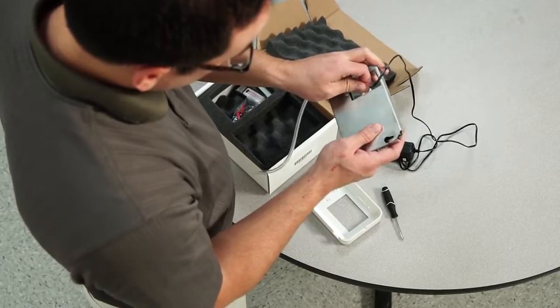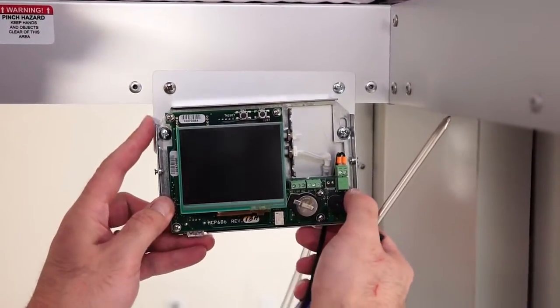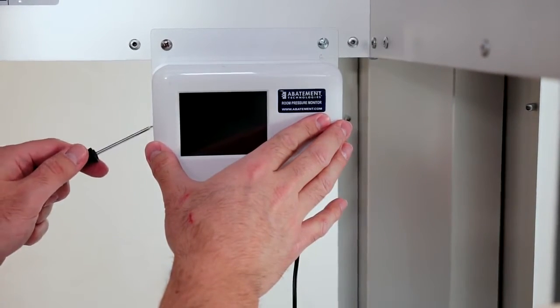Connect the elbow to the bottom port on the pressure monitor, making sure that the tubing feeds through the back of the unit. Loosen the two screws on the pressure monitor mounting plate. Place the pressure monitor on the mounting screws and then tighten the screws to secure the monitor in place. Replace the monitor's faceplate and tighten the two side screws.